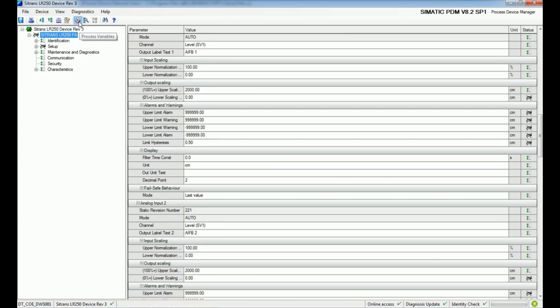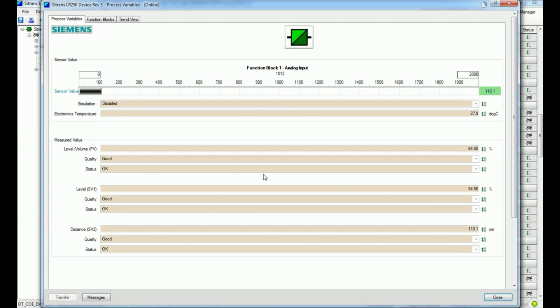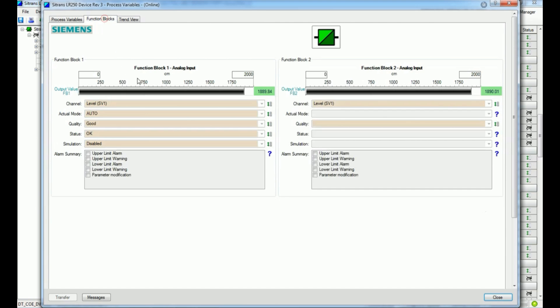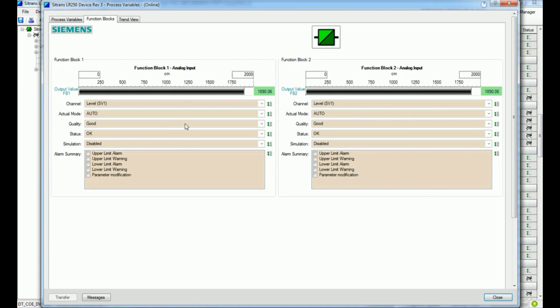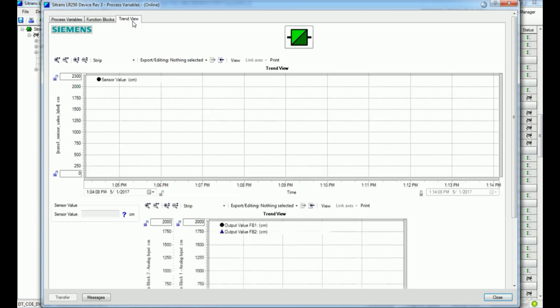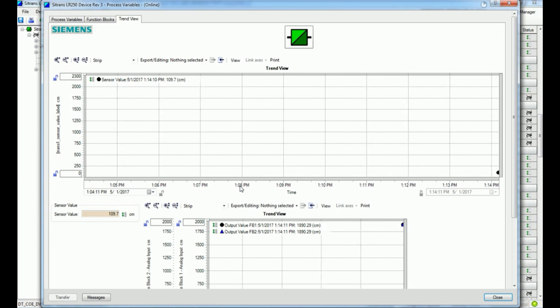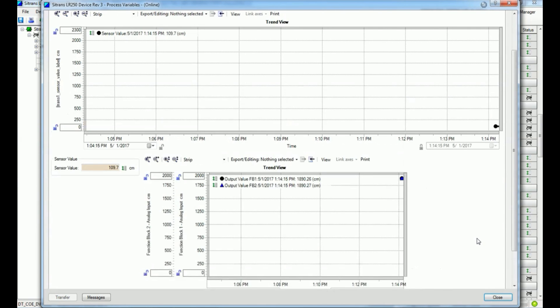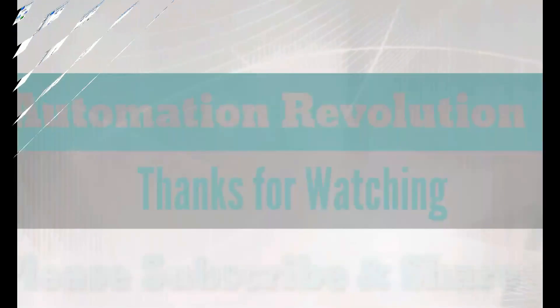We also have the Process Variable option, where we can see the current values changing in real time, along with volume or level type and quality status. In the Function Block section we get information about the level — the analog input coming from 4 to 20 mA signal is shown here. If you change the data levels, the signal will change in the block accordingly. We can also get a trend view showing the level in centimeters over time based on the application.